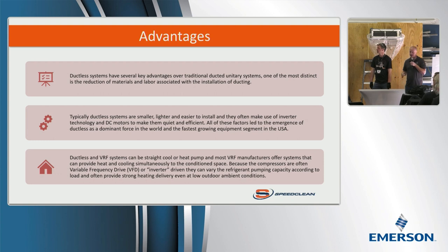They're lighter and easier to install—generally you can install a head and a condenser with a single person. They even make tools that let you pull the unit away from the wall to work on it, and there are different strategies you can use, but generally it reduces labor. The inverter-driven technology also helps efficiency, so the numbers from the factory often look really good. The caveat is that as installed, they don't always perform the way the numbers look on paper, depending on the market and how you install them. So designing and sizing them properly is just as important—and I'd say almost more important in some cases with ductless than with ducted systems.